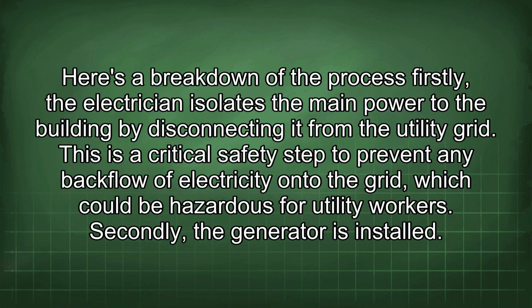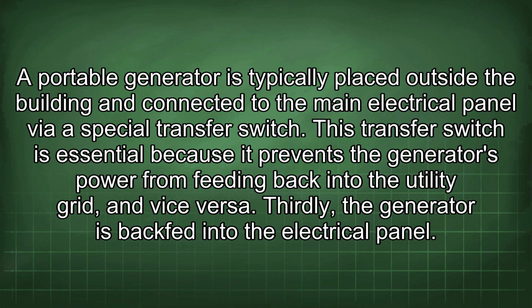Firstly, the electrician isolates the main power to the building by disconnecting it from the utility grid. This is a critical safety step to prevent any backflow of electricity onto the grid, which could be hazardous for utility workers. Secondly, the generator is installed. A portable generator is typically placed outside the building and connected to the main electrical panel via a special transfer switch. This transfer switch is essential because it prevents the generator's power from feeding back into the utility grid, and vice versa.